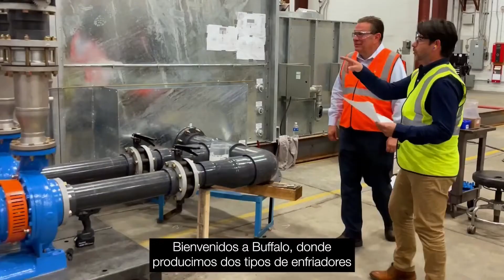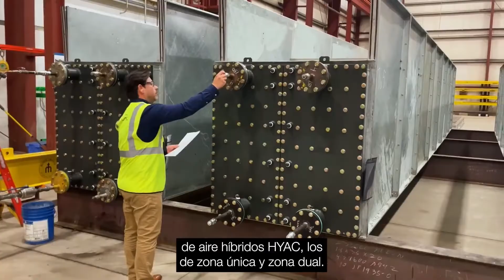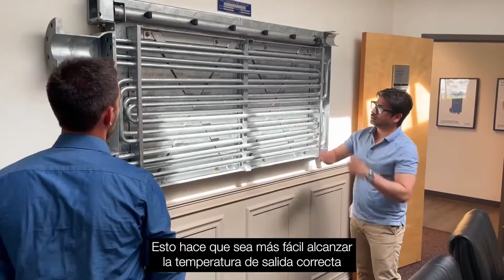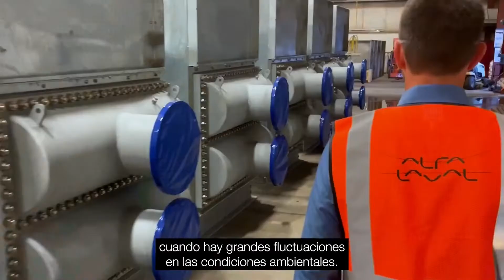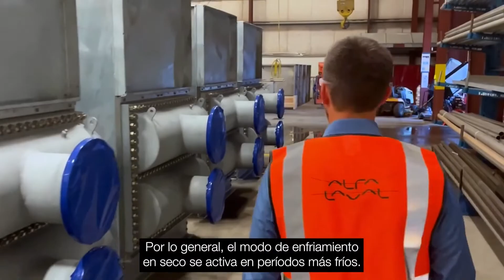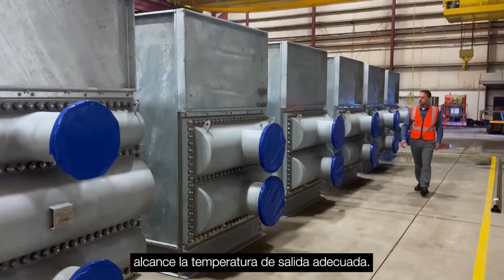Welcome to Buffalo, where we produce two types of HYAC hybrid air coolers, the single zone and the dual zone. The single zone unit is a one-zone cooler that can switch between wet and dry cooling. This makes it easier to reach the right outlet temperature where you have high fluctuations in ambient conditions. Typically, dry cooling mode is activated in cooler periods. This saves space and water while our single zone reaches the right outlet temperature.